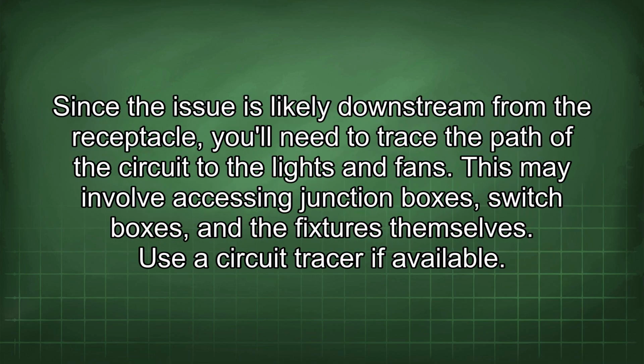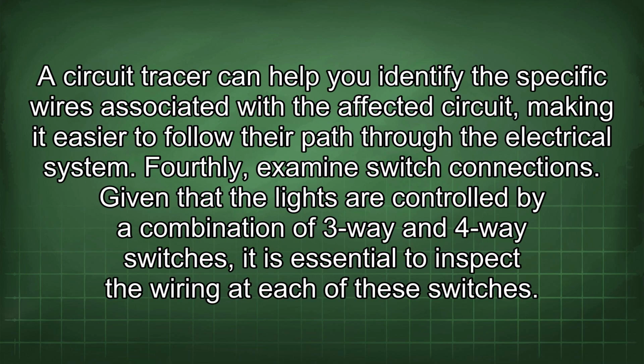Since the issue is likely downstream from the receptacle, you'll need to trace the path of the circuit to the lights and fans. This may involve accessing junction boxes, switch boxes, and the fixtures themselves. Use a circuit tracer if available. A circuit tracer can help you identify the specific wires associated with the affected circuit, making it easier to follow their path through the electrical system. Fourthly, examine switch connections. Given that the lights are controlled by a combination of 3-way and 4-way switches, it is essential to inspect the wiring at each of these switches.